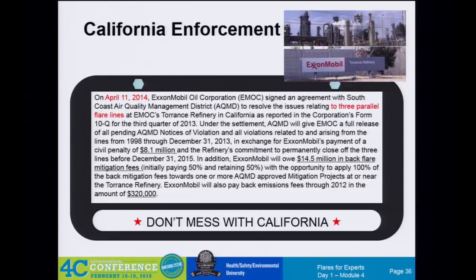Last year, April, this was really quiet, many of you may not even know this happened. There was an signed agreement with South Coast. They had three flare lines going to two different flares, so multiple connections to two flares, operated kind of as a cascaded system. Routinely, the system has a flare gas recovery sucking lots of material back in for reuse. They have a low flow enclosed combustor, that's not a flare, it's an enclosed combustor for the low flow case. And then during the oh-my-God moments, the big flares go off.